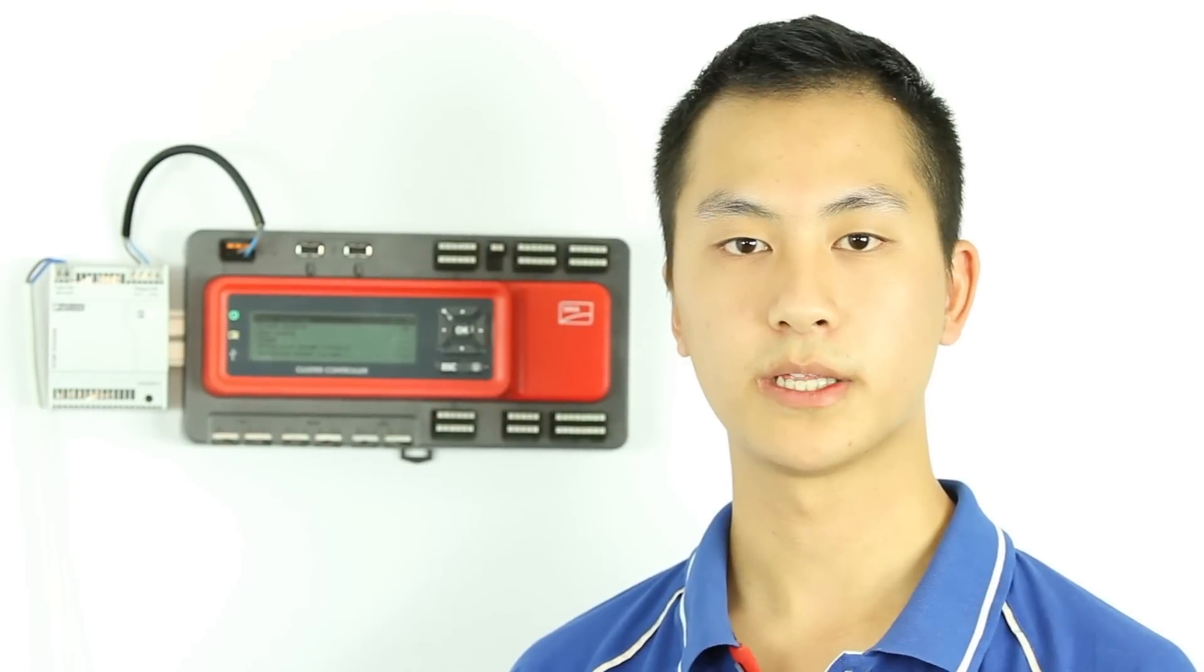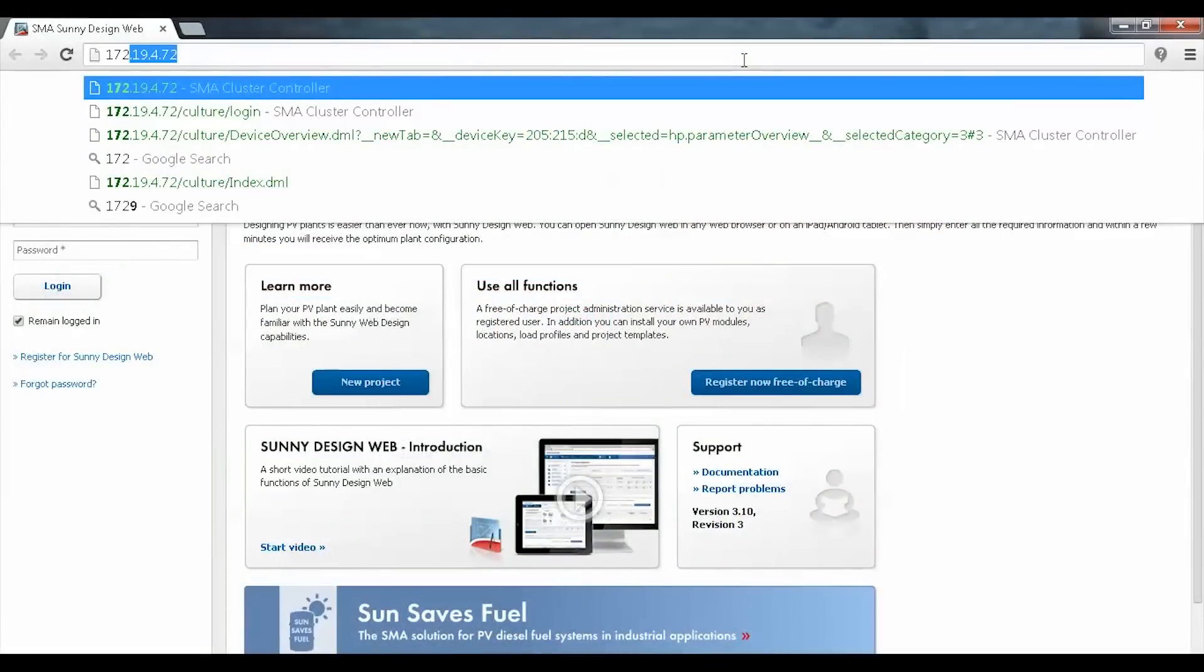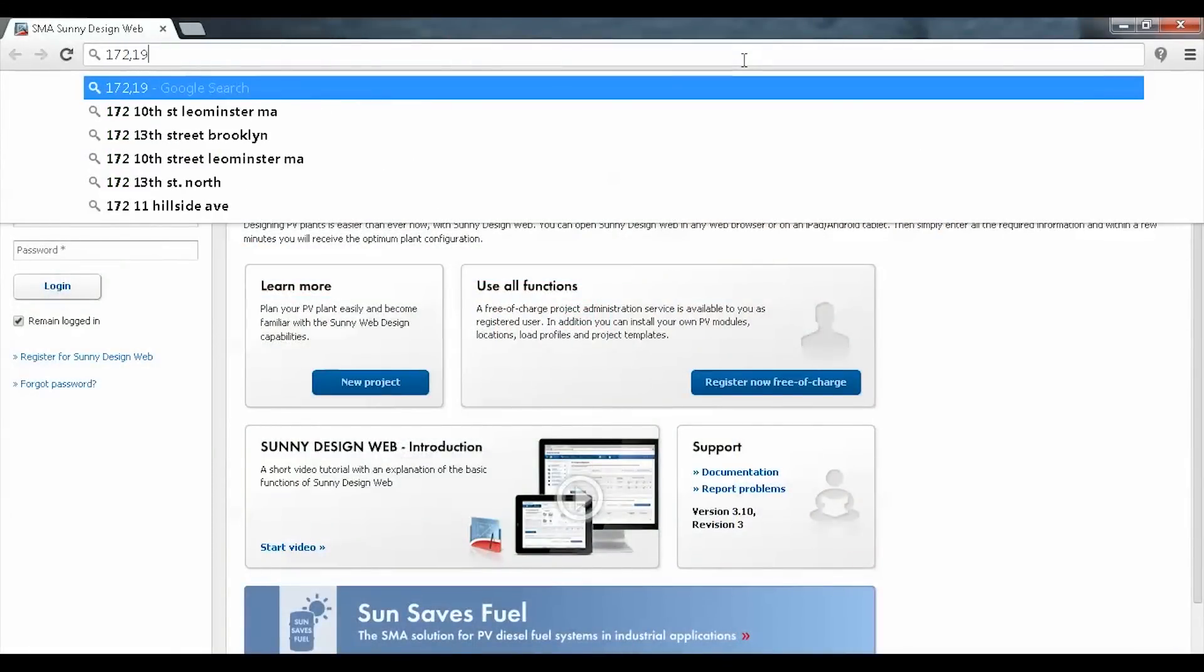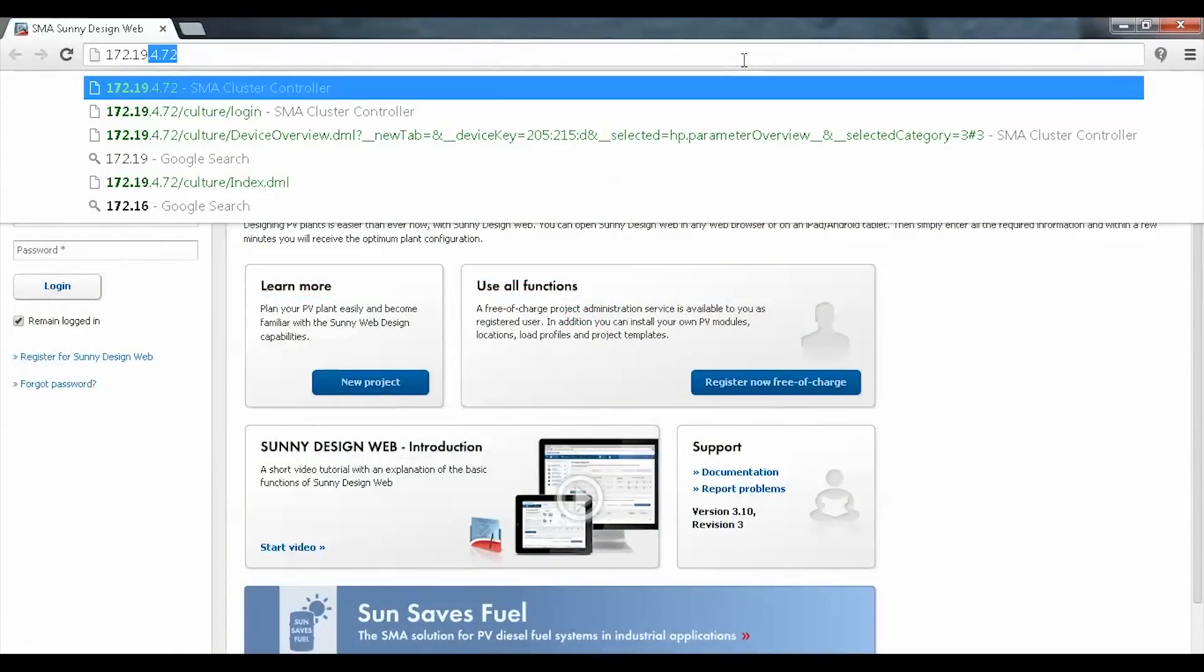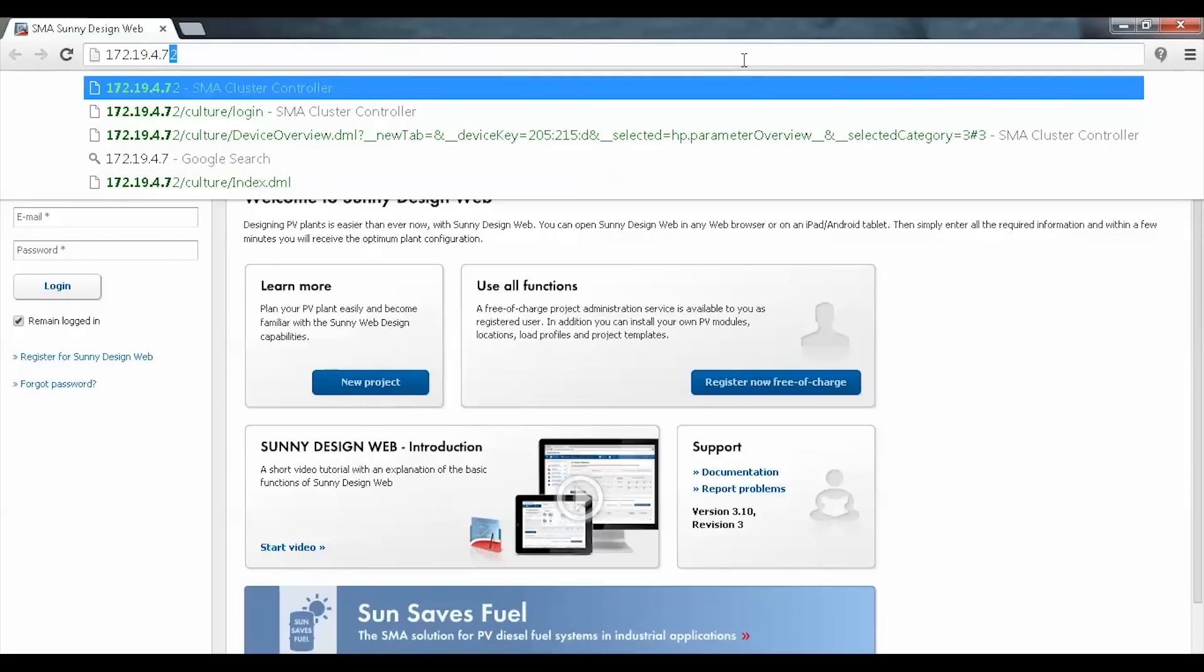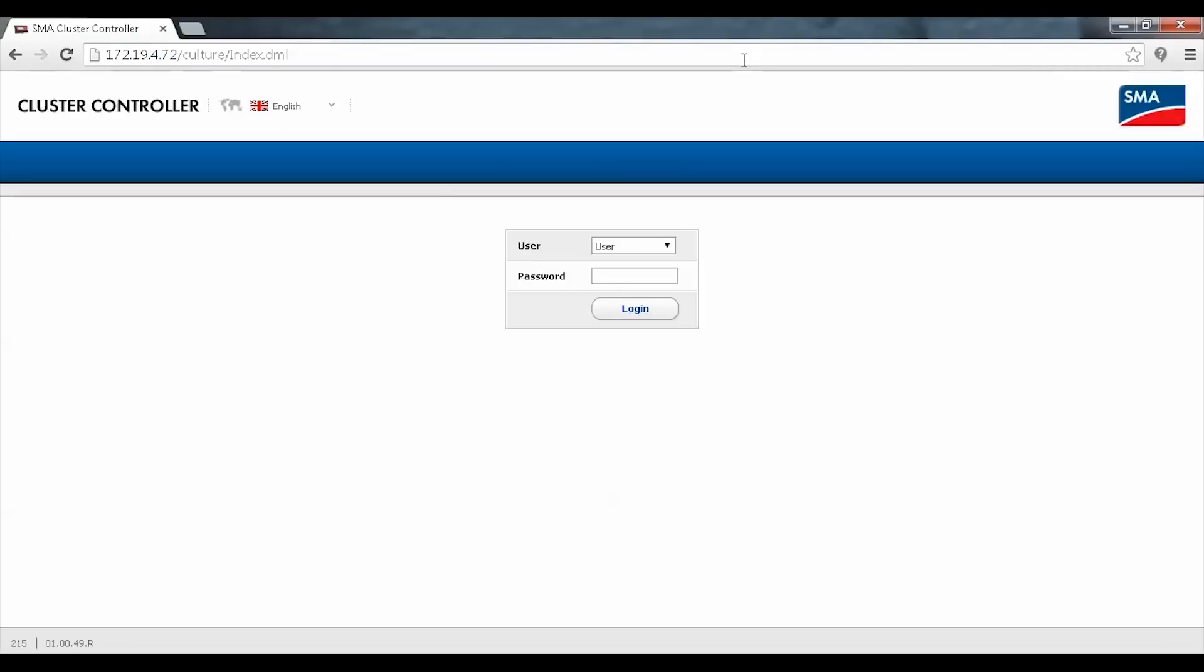Now we'll have a quick look at the web interface of the Cluster Controller. You'll be able to find the IP address of the Cluster Controller on the display under the LAN communication section. From here, the default password for the user is 0000 and for the installer it's 1111.